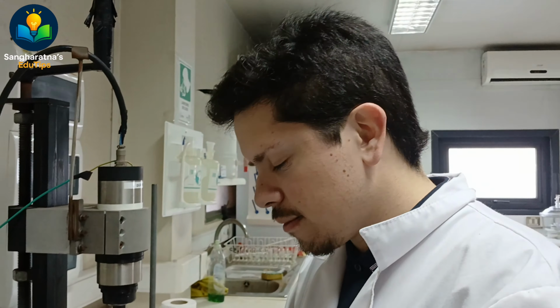We're gonna go into utilities, then calibrate instrument, and say OK, because this is a potentiostat. We're gonna calibrate both types, both for DC and AC. I'm gonna go OK. Then it will ask for some information and for some clearances, which are connecting your cell leads to the calibration side of a universal dummy. And this is OK. Unit should be fully warmed up, and it should be. And now we're gonna start the calibration. And that's it. We gotta wait now 8 minutes, and then it will be ready. And now this is calibrating.